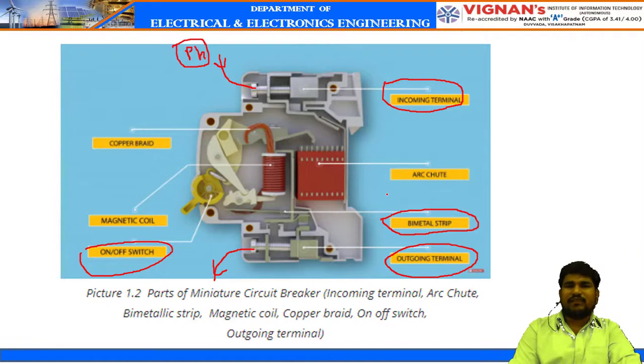During fault conditions, the current suddenly increases. Within no time, the current reaches multiple times the rated current. If we still use the bimetallic strip for the short circuit current, what happens? The bimetallic strip will take some time to expand. As it is a mechanical component, it will take time to expand when a fault occurs. In this time, the connected equipment will be damaged by the fault current. Then what is the use of a circuit breaker if it does not protect from short circuit faults?